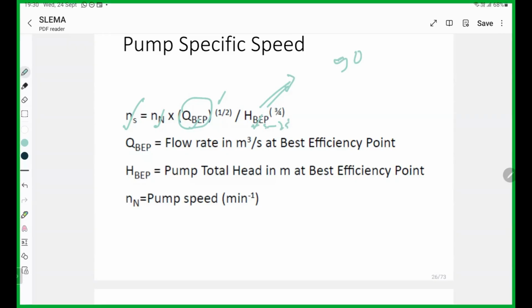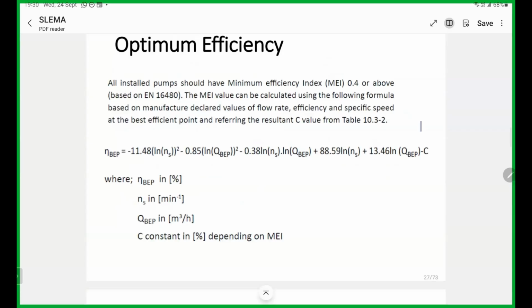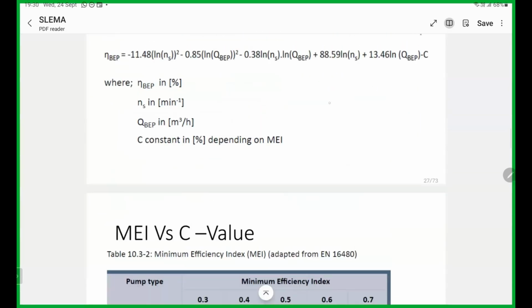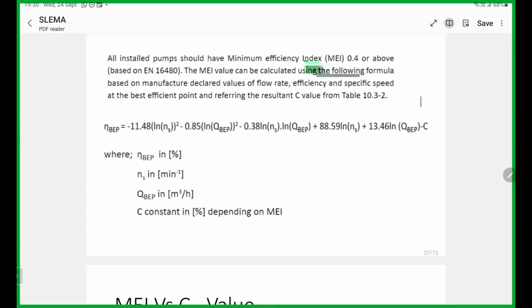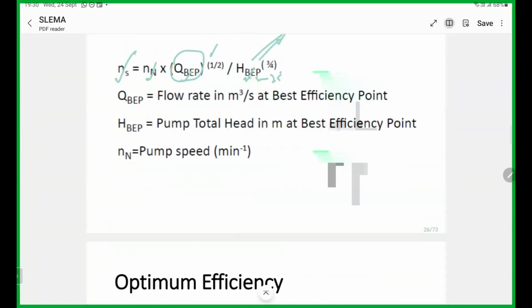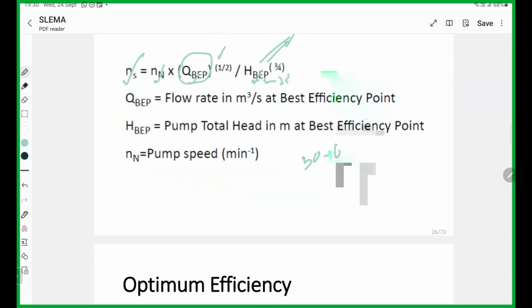Before selecting the pump, you have to calculate the Ns, right? Very important is Ns. Generally, you have to keep the Ns in between 30 to 60. It is a general idea, right? Then you can select the best market-available efficient pump. You can change Ns by changing the RPM, 3000 or 1500, or on 50 Hz. Then you can select your pump, and you can change the number of impellers and optimize this Ns.